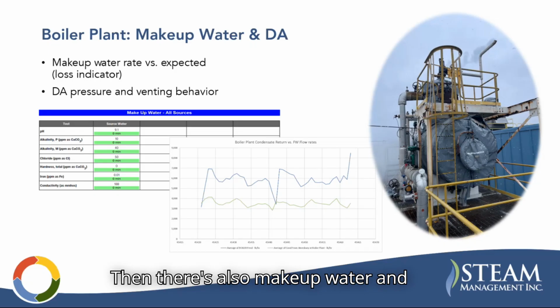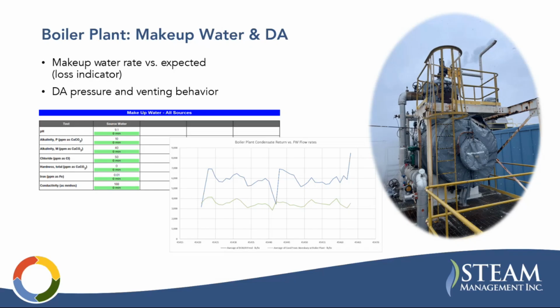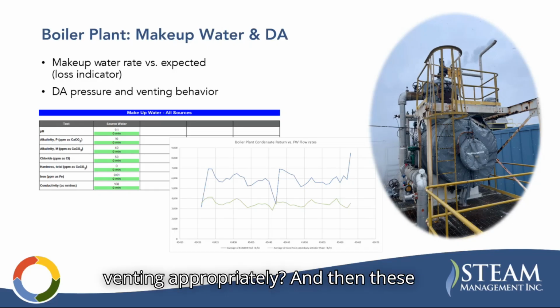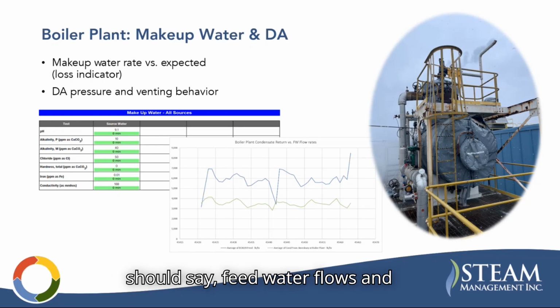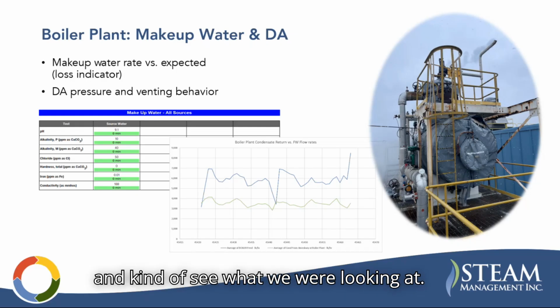Then there's also makeup water and deaerator improvement opportunities. We're evaluating, is the makeup water rate what we would expect? And then is the DA pressure optimal? Is it venting appropriately? And then these photos are just a water quality analysis. This is where we were able to take boiler operator logs, feed water flows and condensate return, and model that out and see what we were looking at.